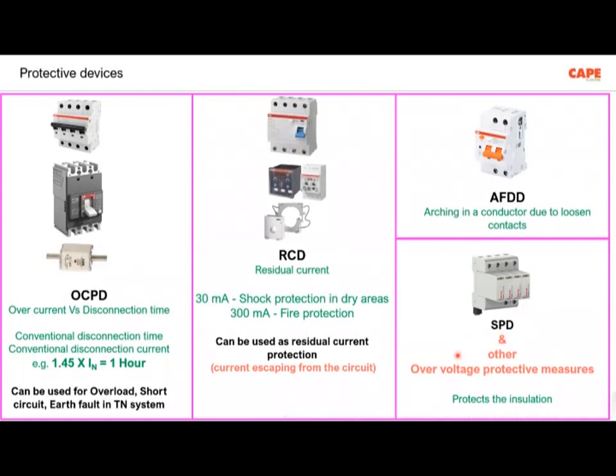Say, for example, as I said in the previous slide, a fault on the high voltage side of the transformer can create a failure and a shock hazard inside our house. So the maximum overvoltage allowed inside our building is 1200 volt for 5 seconds. More than that is not allowed, and we need to implement all these protective measures in our building. So I would recommend that the electrical designers listening to this program start looking seriously into this particular subject.